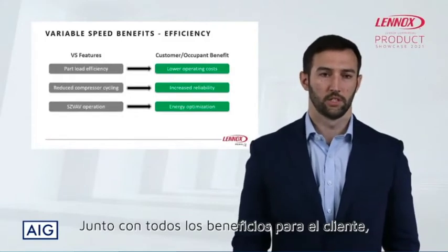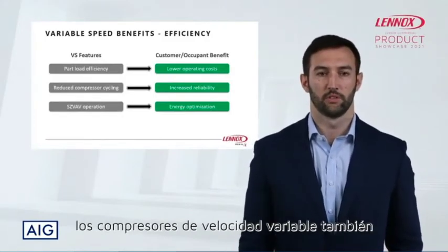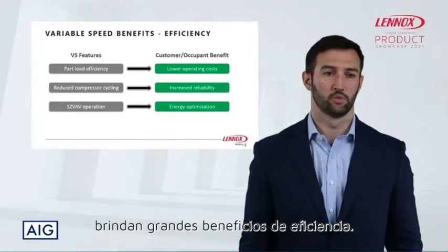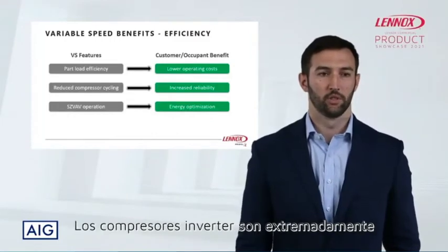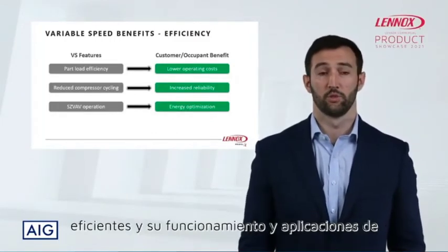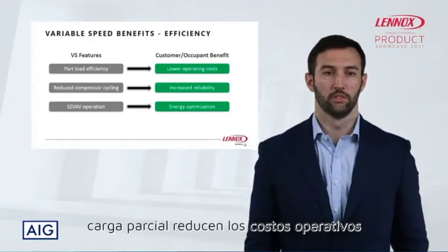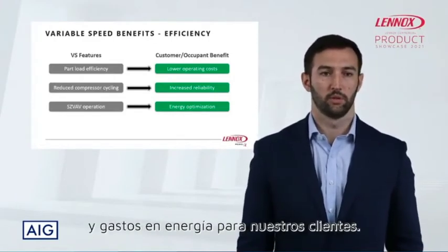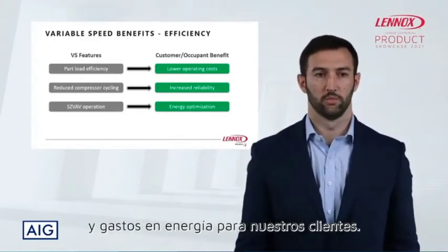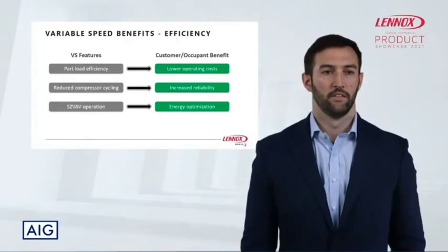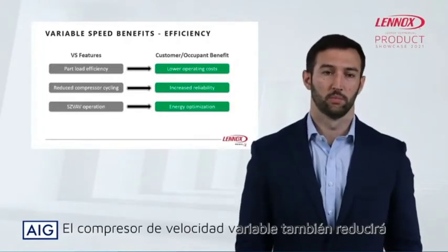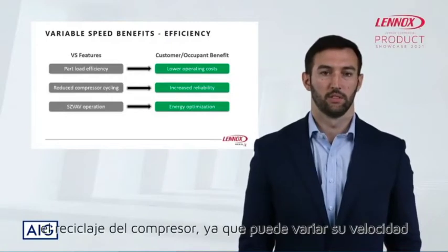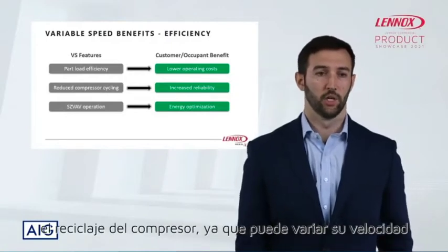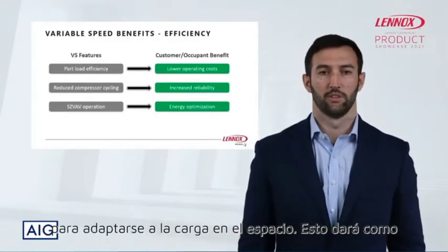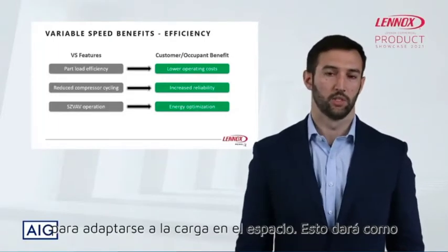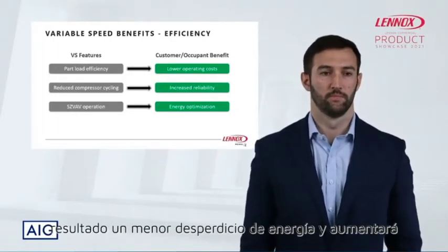So along with all the customer benefits, variable speed compressors also provide great efficiency benefits as well. The inverter-driven variable speed compressors are extremely efficient in part load operation and applications, which reduces operating costs and lowers energy bills for our customers. The variable speed compressor will also reduce compressor cycling as it can vary its speed to match the load in the space. This is going to result in less wasted energy and increased reliability for that customer.